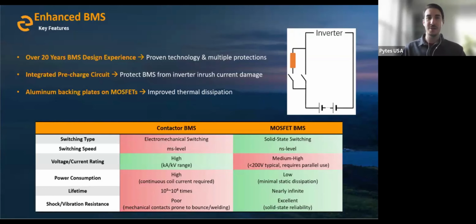What the pre-charge circuit does is essentially a resistor that connects the battery pack to the inverter's capacitor before the actual cells. It allows the inverter capacitor to slowly energize. It sort of bleeds voltage into the inverter and lets the inverter capacitors catch up to the level of the batteries. Once they're at the same voltage or very close to each other, it switches over and connects the batteries to the inverter, and now you've avoided that high inrush current surge that can sometimes happen.